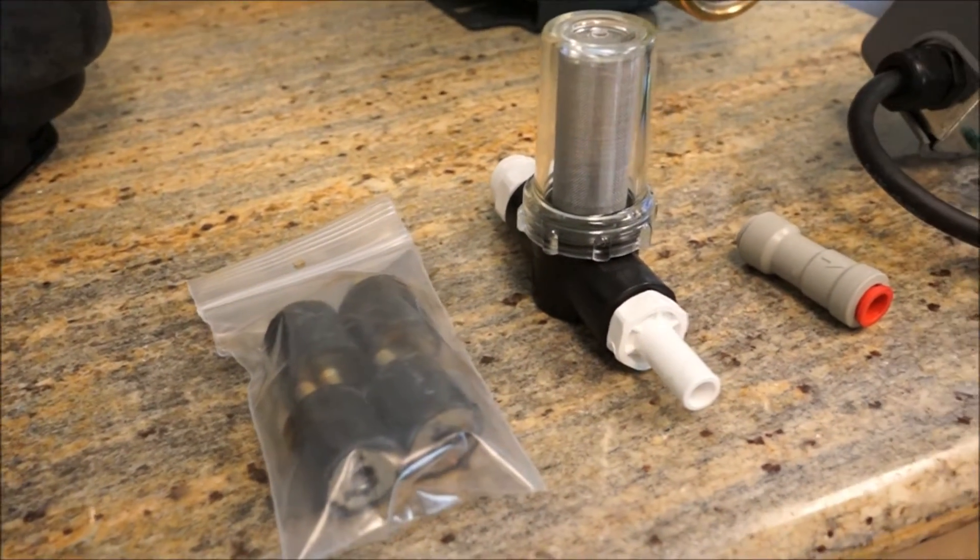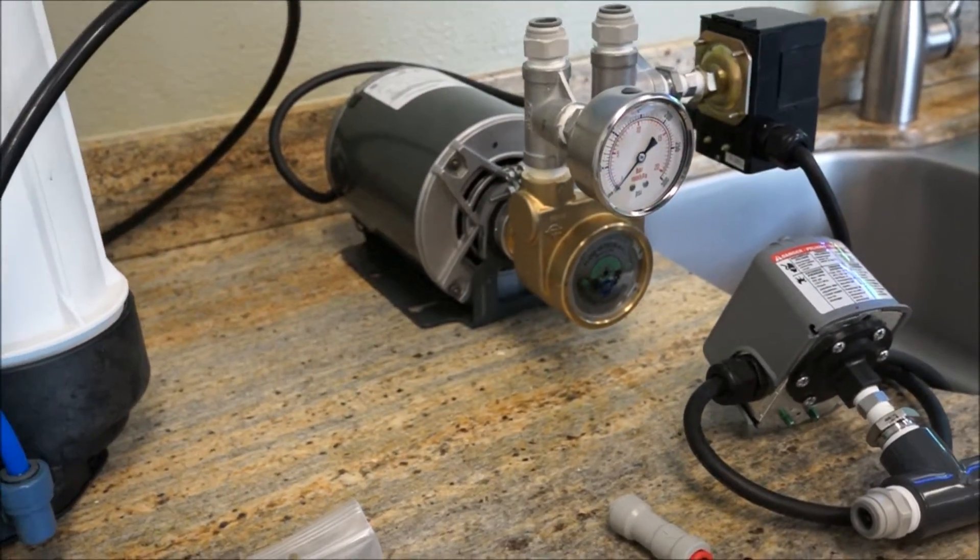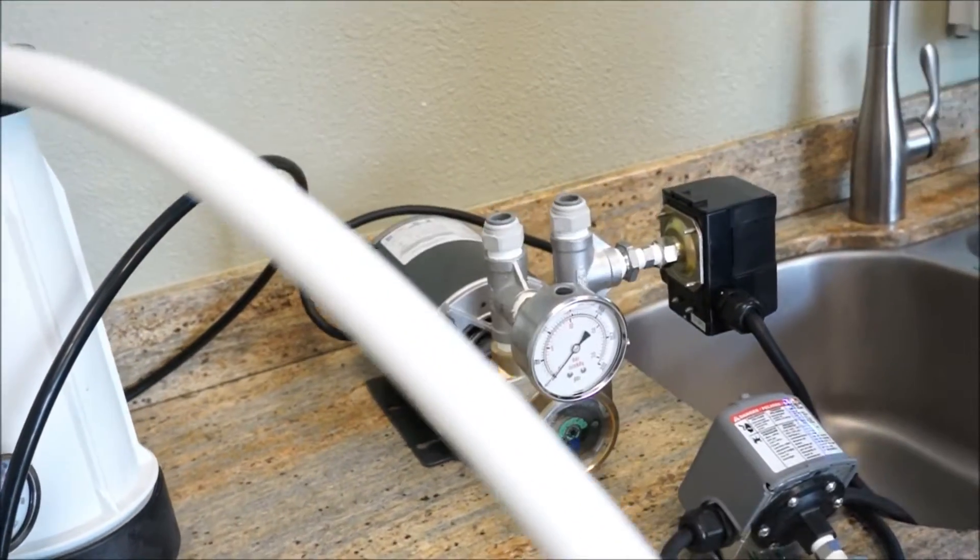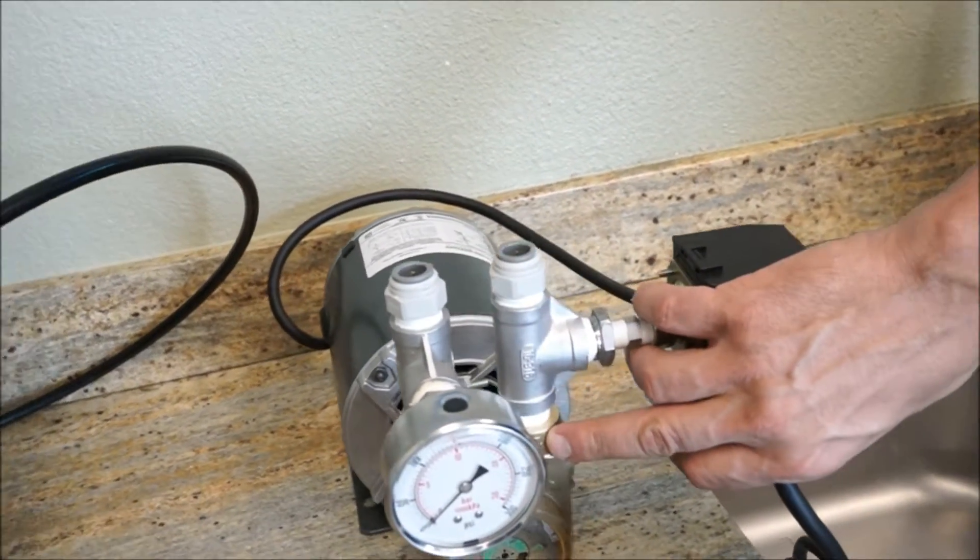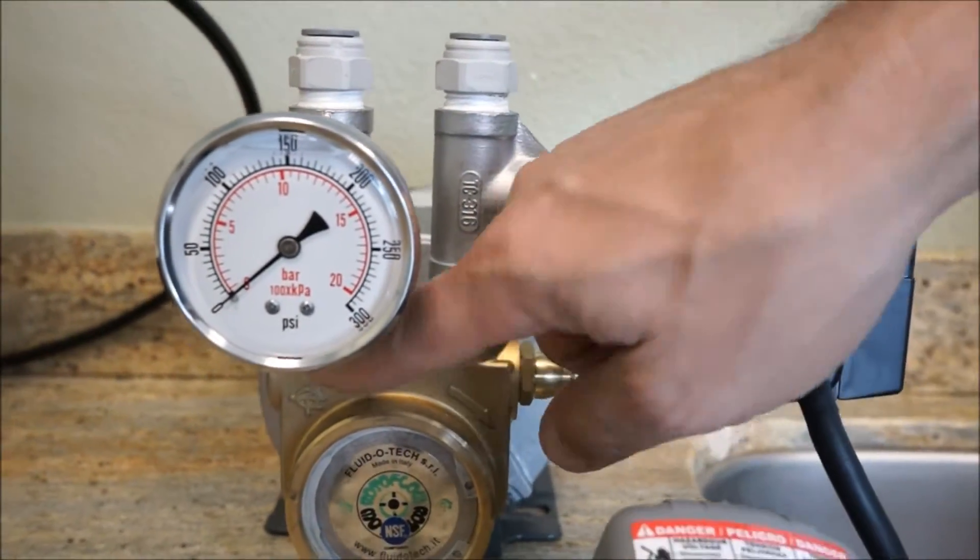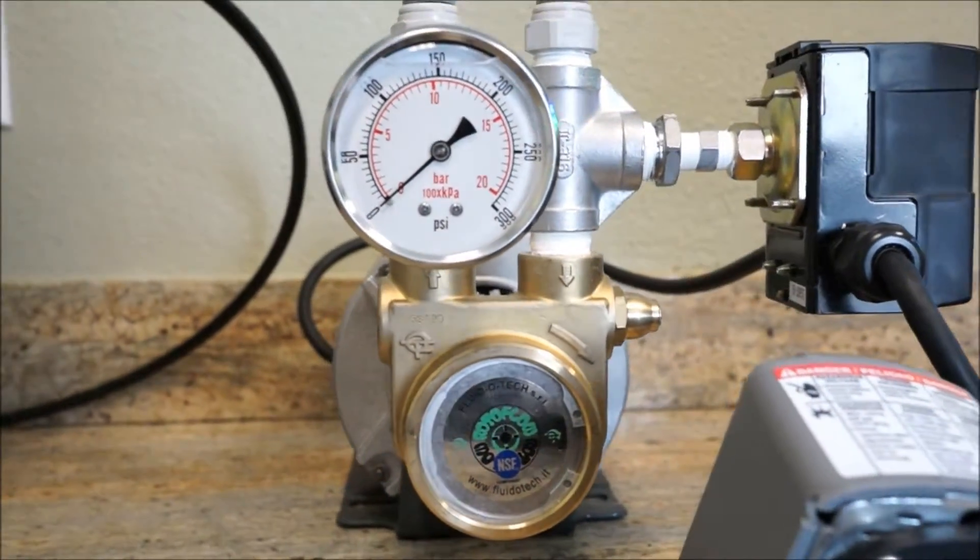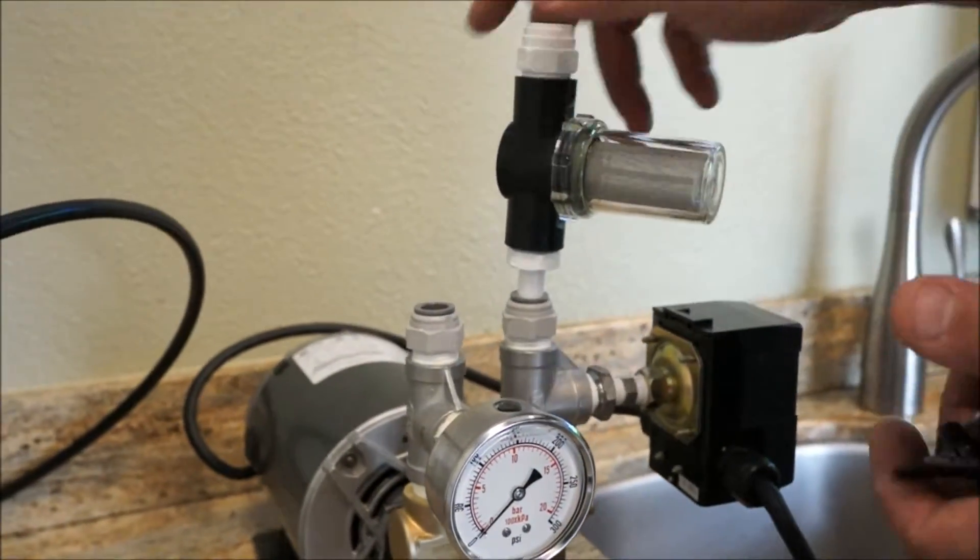The first thing you're going to want to do is take your pump protector filter and push it into the inlet of the pump. You can see that there is an arrow on the actual pump itself. The down arrow meaning that's the water that comes in and then the up arrow is the water that goes out to the unit itself. So this is your inlet. You're going to push this right in.